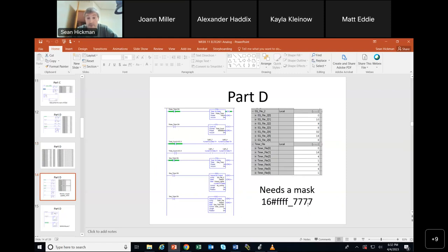All right, now here's what's important, once again, that you want to be sure you understand the mask and the way this works. I am right here pushing out numbers to the output module. The file, this 10 right here, or this 32, or this 16, or whatever, it's ones and zeros. Those are going to the output module. So every bit on the output module, there's 16 outputs, is getting a 0 or 1. We're telling the light on the output module to turn on. Every single one of the 16 of them to turn 0 or 1.